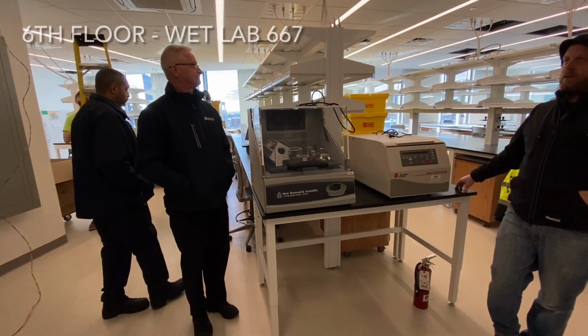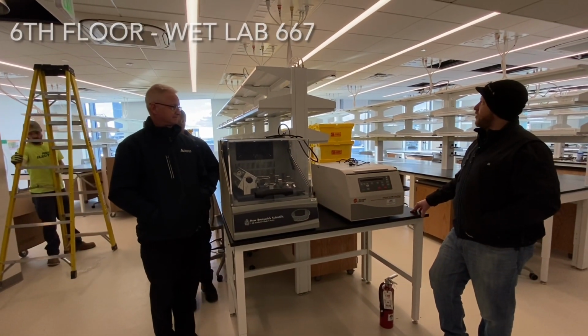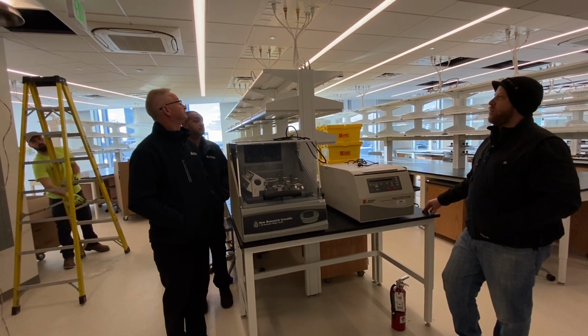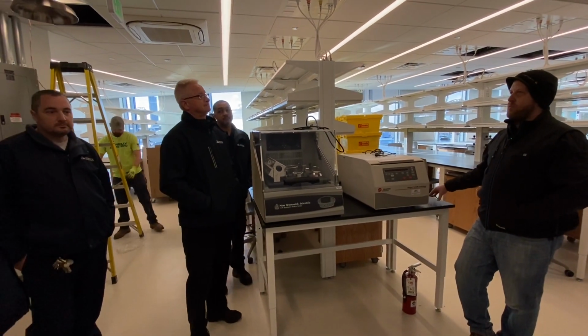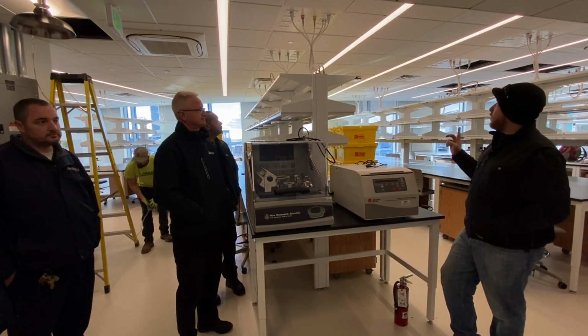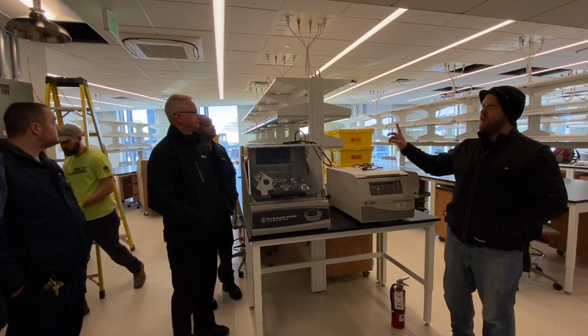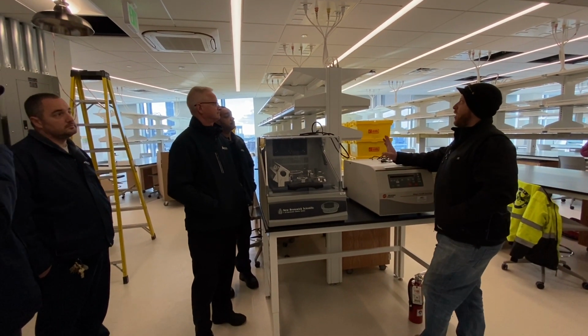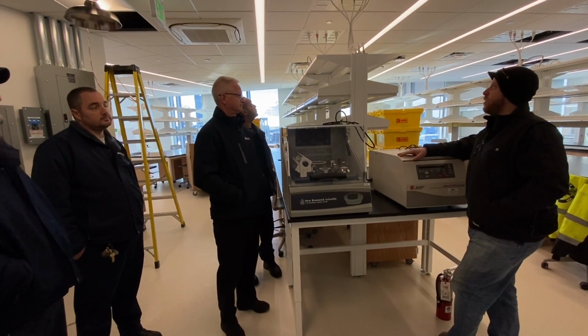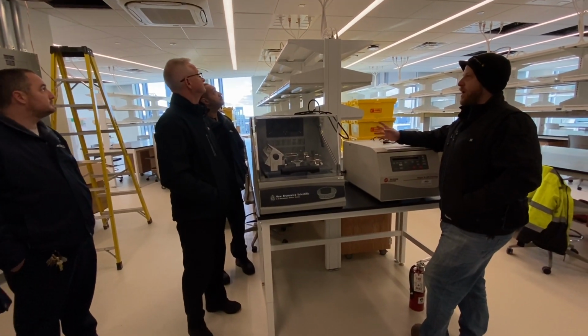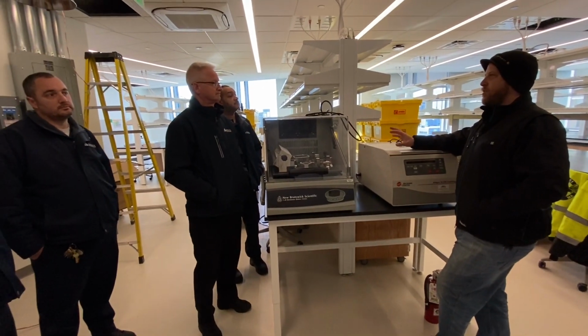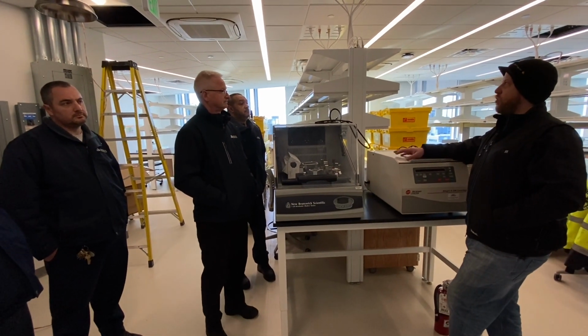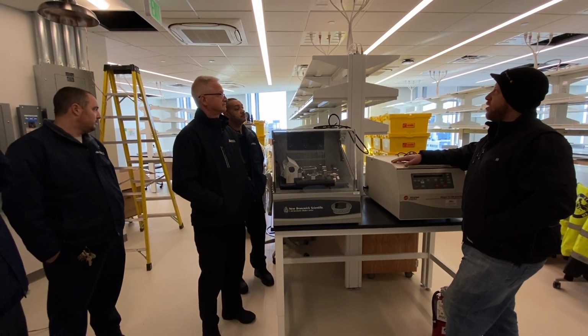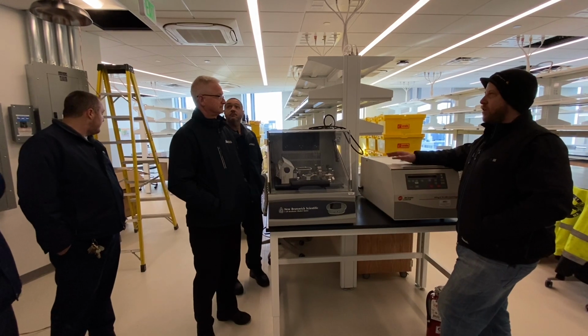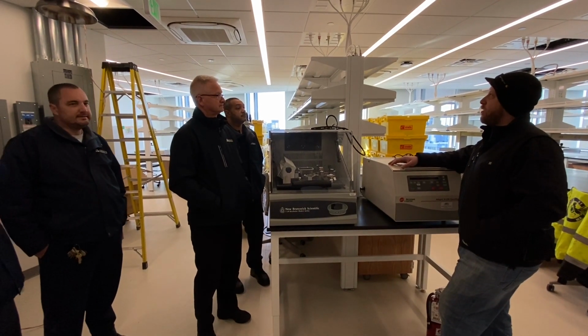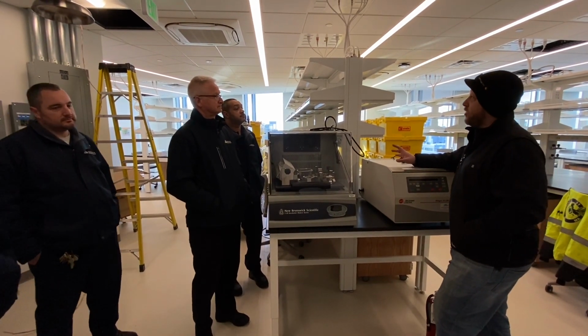Okay, so the wet labs are kind of interesting. So again, as I said, DOAS 1 gets you all the fresh air, but what they did is install a Mitsubishi VRF system for the primary heating and cooling, and that has its own. We're monitoring it, but it's controlled pretty much on its own. You can send it some commands from the BMS to be either in heating or cooling, there's some things you can change in set points. It'll give you a change-of-filter alarm. So there's some things you can do on the front end, but mostly it's its own package controller.